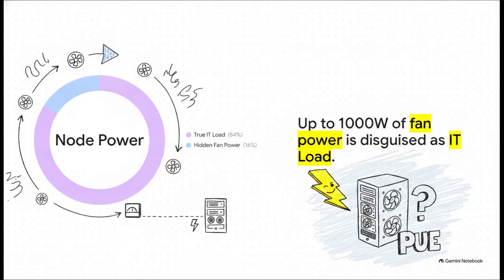But here is the hidden tax. Air-cooled servers totally cheat the PUE metric. Up to 1,000 watts of embedded fan power is buried right inside the server chassis. Because those screaming little fans are physically inside the node, drawing power at the server level, their massive electricity consumption gets counted as IT load. It is completely disguised as productive compute power, when in reality it's just cooling overhead.